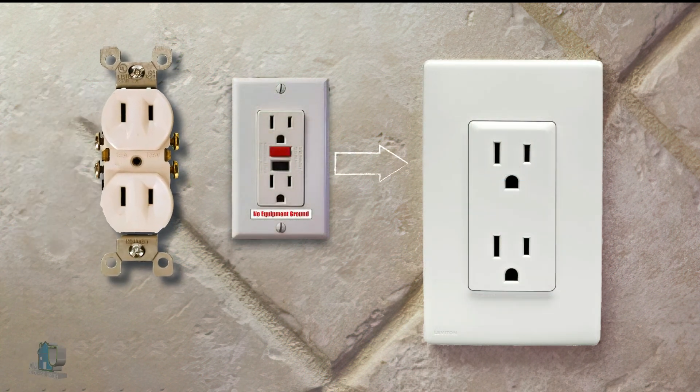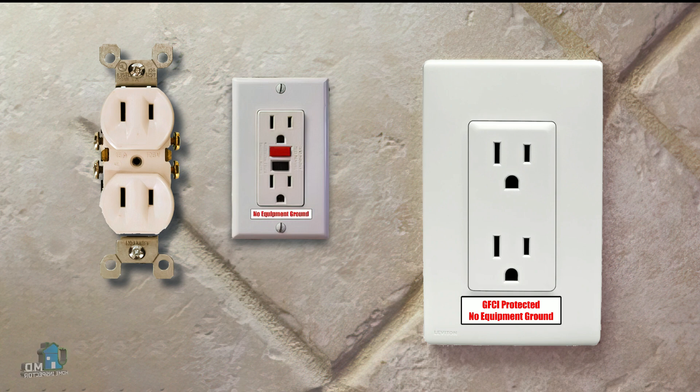As we have stated, you can use regular three-prong receptacles downstream from a GFCI and those will also be protected.